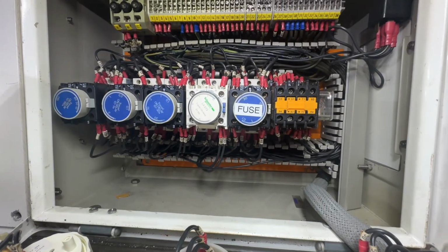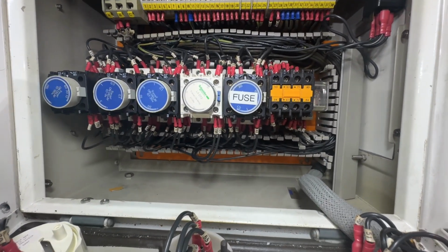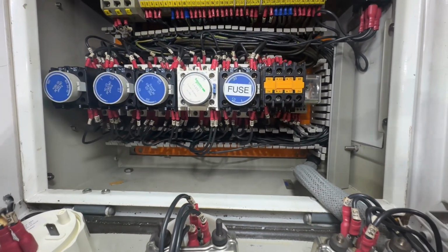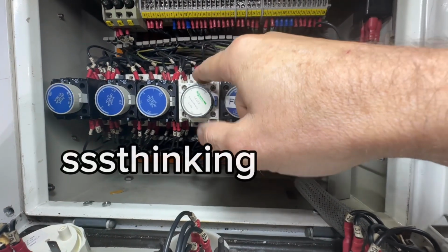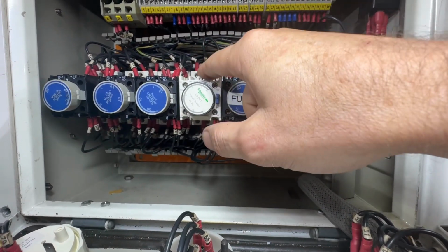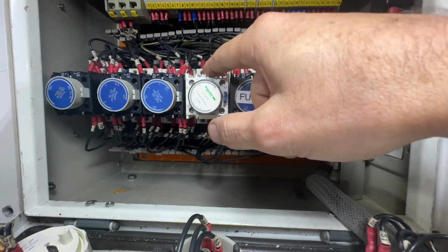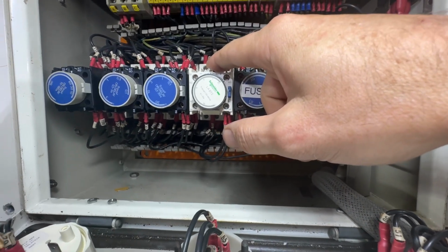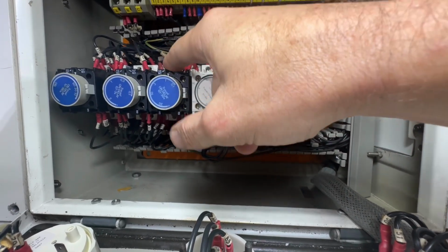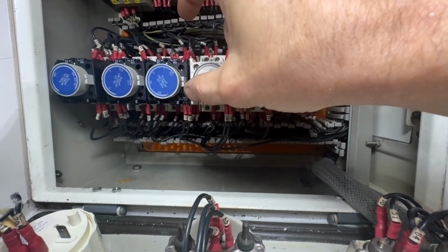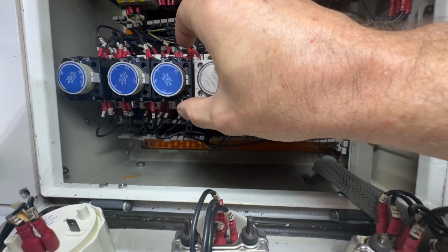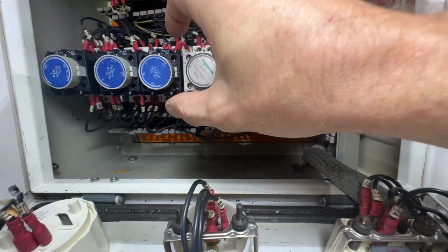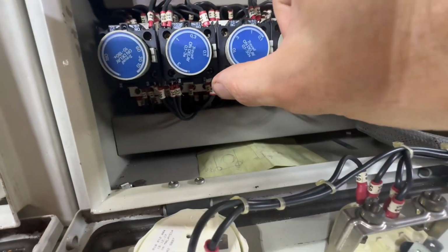So I think I just figured out something that's going to help until we get the problem truly solved. I had been thinking this was the problem. This is the contactor or relay that actually engages the starter. But it turns out this particular contactor is not getting power to the coil the same way that the one in the working generator is.